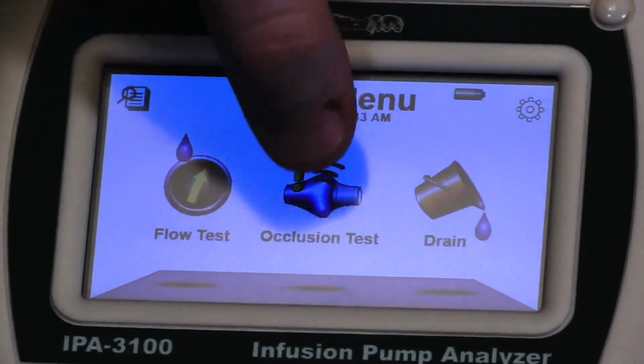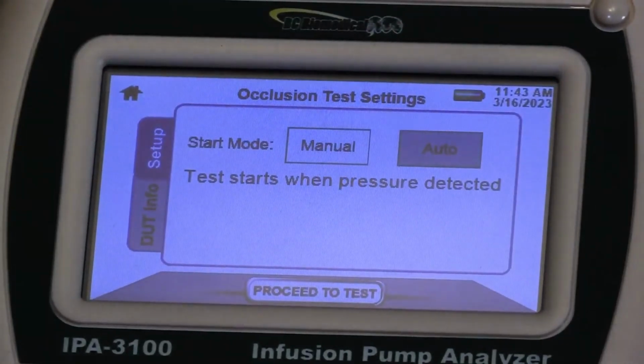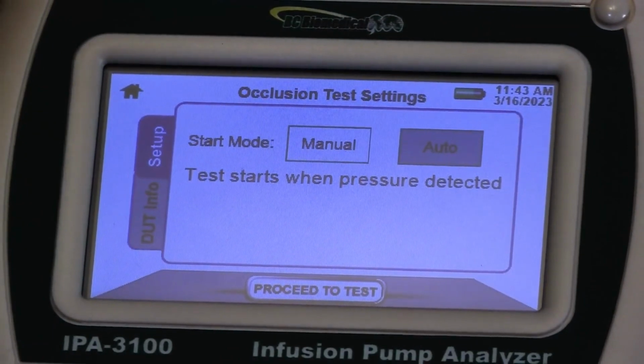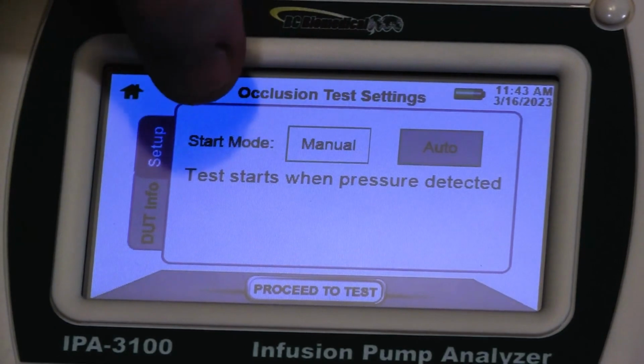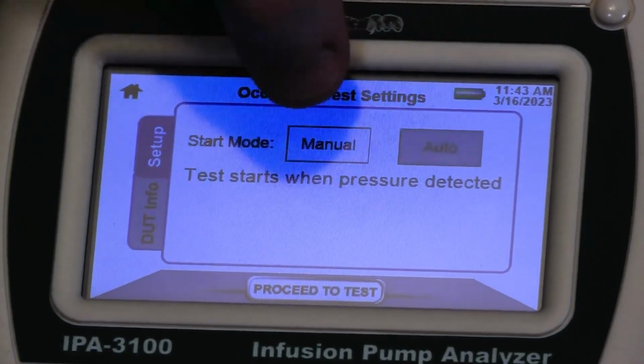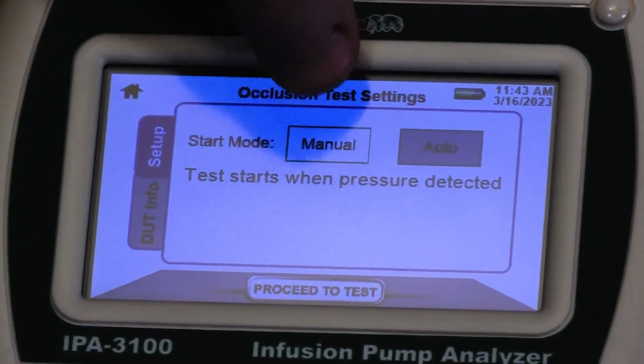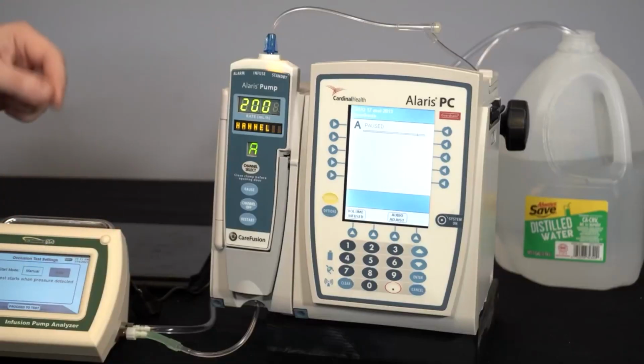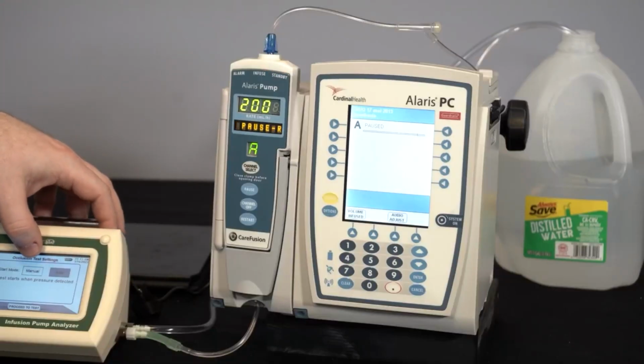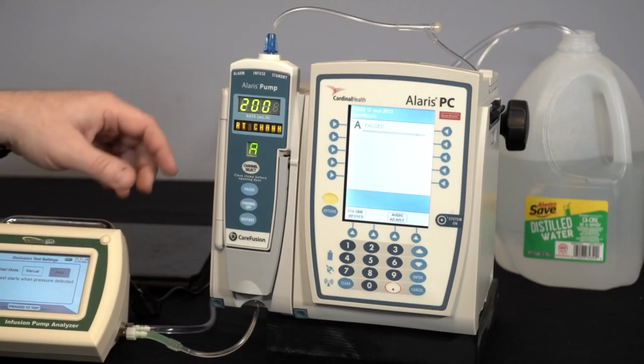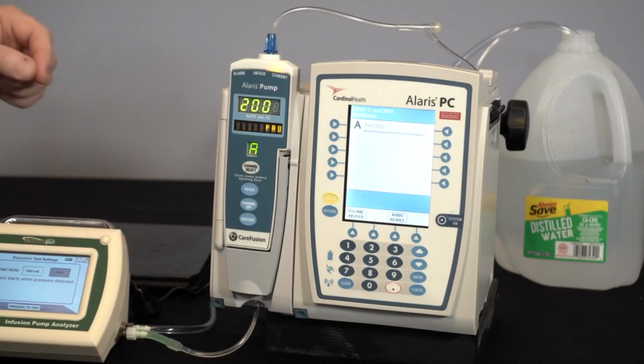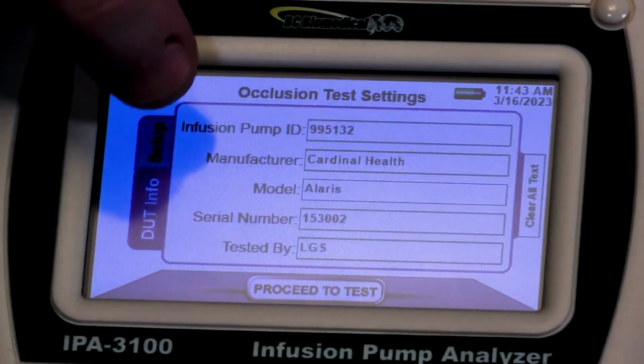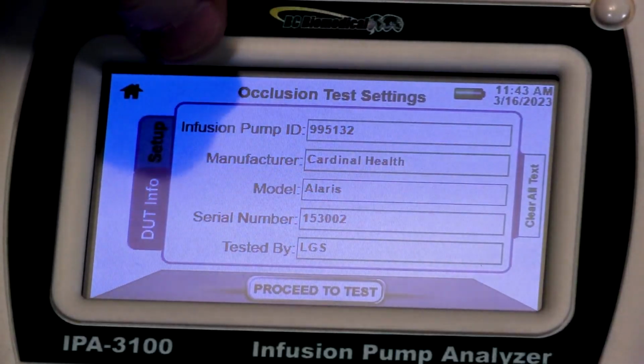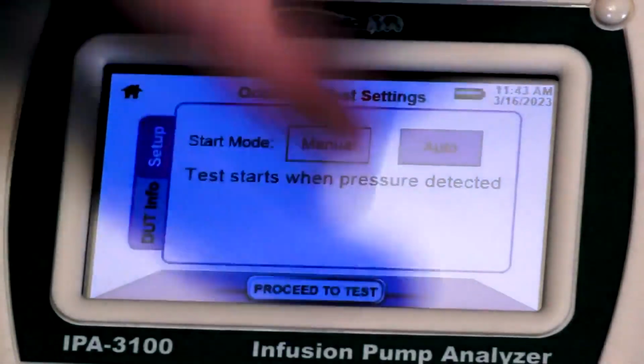To perform occlusion testing, we select Occlusion Test from the main screen. We already have our tubing primed and the pump ready to run. We have the option of selecting either manual or auto start mode. Just like the flow test, the manual test will immediately start counting time as soon as I start the test. The auto mode will wait until it detects flow from the pump before it runs the timer. I can also enter the information about the device under test that I'm using. And I press start. And that takes me to the testing screen.